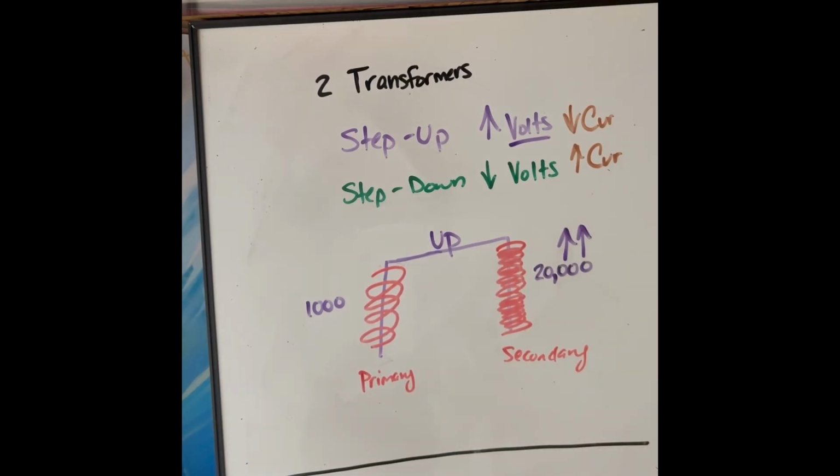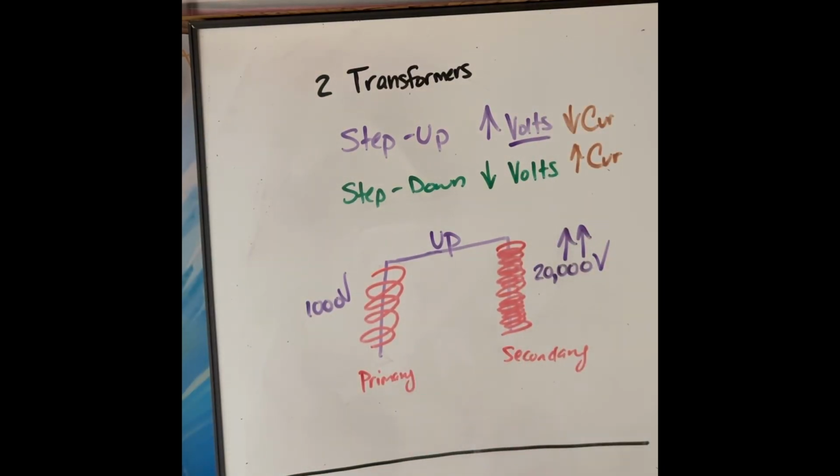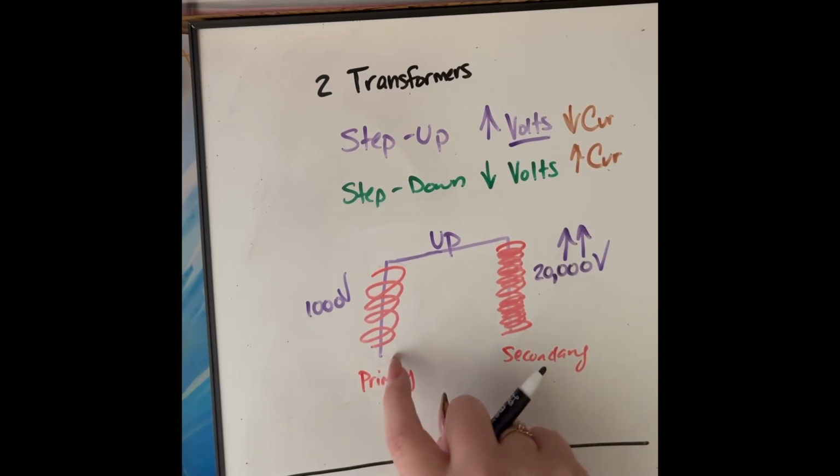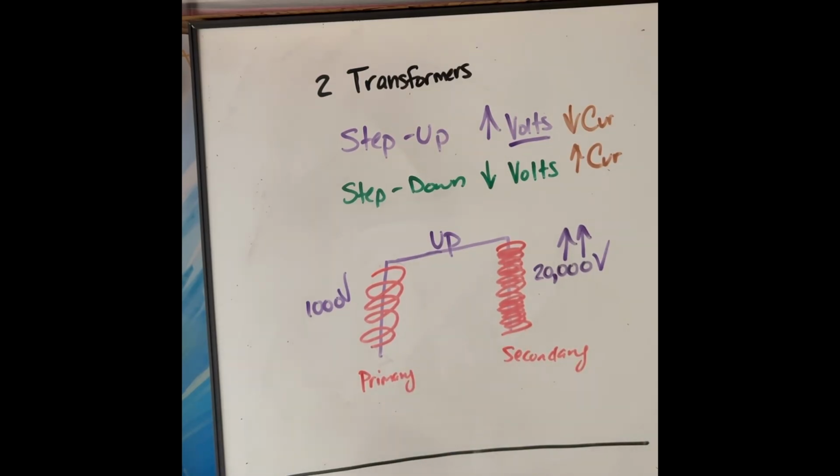And this is going to be what supplies our voltage to our anode. That anode would become more positive and attract all of those electrons over from the cathode. But regardless, our step up transformer is going to allow our voltage to go up. If I'm looking at just a diagram, I can't see my voltage here at all. What would I see? I would see more windings on the secondary side than the primary side. That would tell me this is a step up transformer.